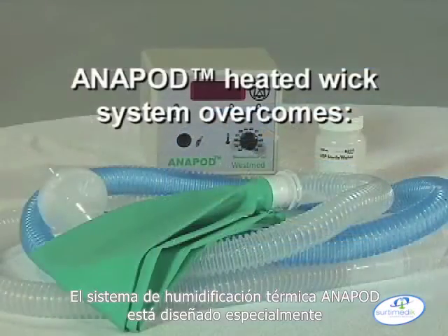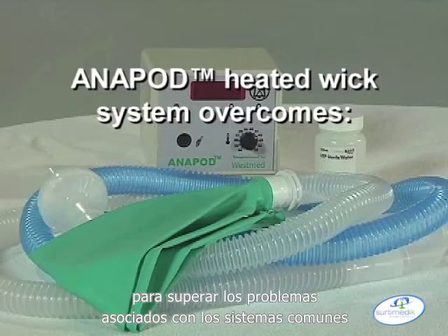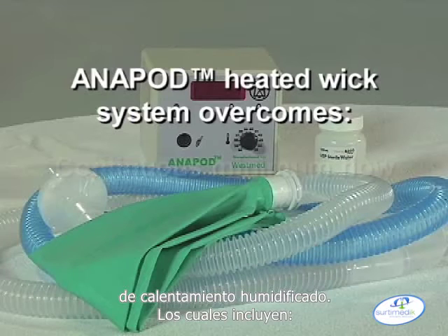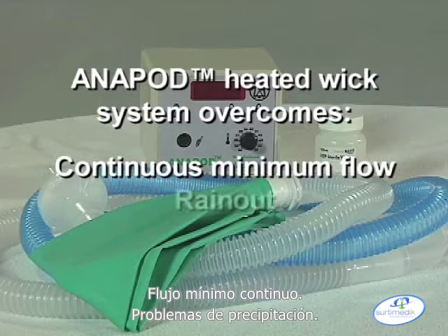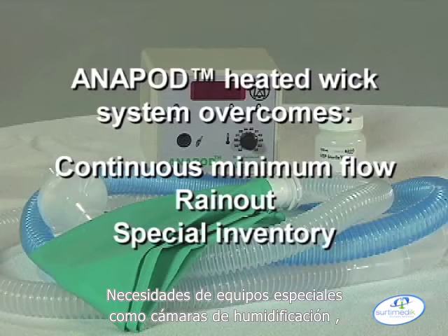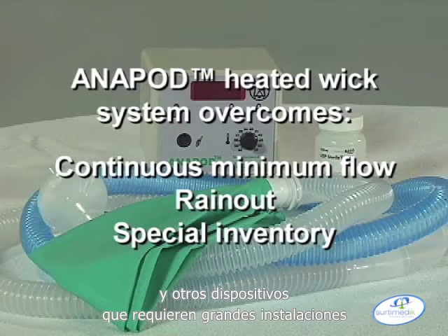The heated wick breathing system is uniquely designed to overcome the problems associated with common heated humidification systems, which include continuous minimum flow, rainout, special inventory requirements such as water chambers, and other devices that require lengthy setup and warm-up.